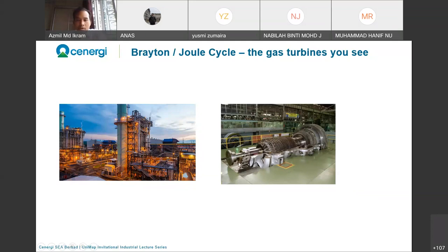So what they do is they open the top casing, and after that they dismantle a few things, and then you can take the shaft out, but you cannot transport it out. So what you do is you lift it up. There's a crane over here, a double girder crane, that moves throughout the whole hall. It lifts the shaft up and puts it to the side on a proper casing. That's where you do the maintenance for it. You do the rotation, the balancing, the alignment. It's a specialist job.